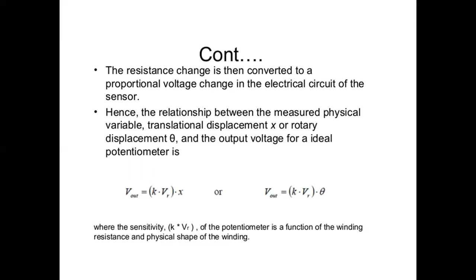Okay, and when you are talking about the resistance change, it creates a proportional voltage change in the electrical circuit of the sensor. So the relationship between the measured physical variable, translational displacement x or rotational displacement theta, and the output voltage for an ideal potentiometer is given as k into VR into x, or k into VR into theta. Here the sensitivity k into VR of the potentiometer is a function of the winding resistance and the physical shape of the winding.